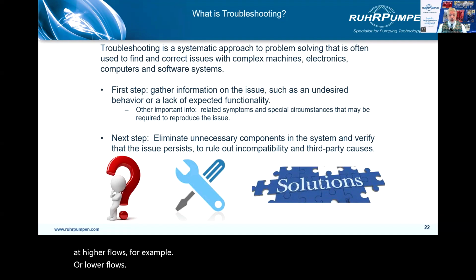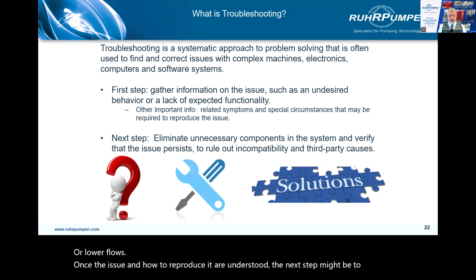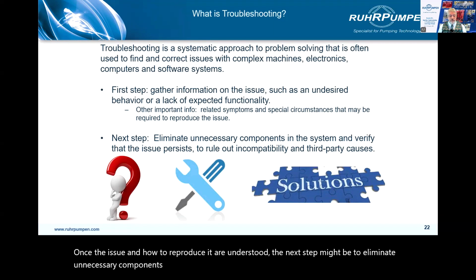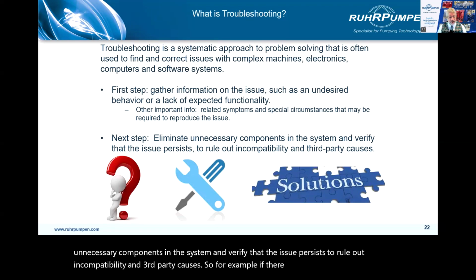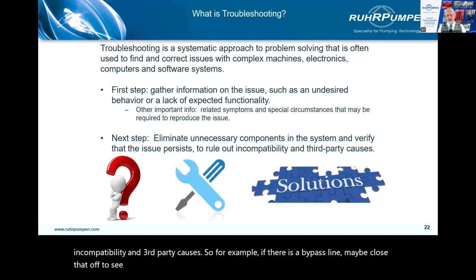Once the issue and how to reproduce it are understood, the next step might be to eliminate unnecessary components in the system and verify that the issue persists, to rule out incompatibility and third-party causes. So, for example, if there is a bypass line, maybe close that off to see what effect this has on the problem.